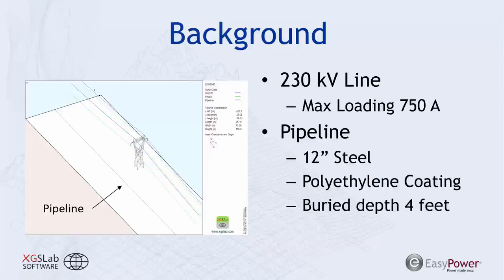So I have a model in XGS Lab of a 230 kV transmission line with an H-frame orientation of the phase conductors, and each of those phase conductors has 750 amps of balanced load. And I have a pipeline that's approximately 50 to 60 feet away from the closest phase conductor, buried 4 feet into the earth, and has a polyethylene coating to insulate it from the soil. The soil resistivity is 50 ohm-meters, so relatively low, and that, as you'll see, can cause issues for the AC corrosion that we talked about as a pipeline concern.